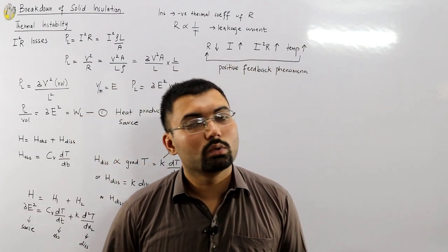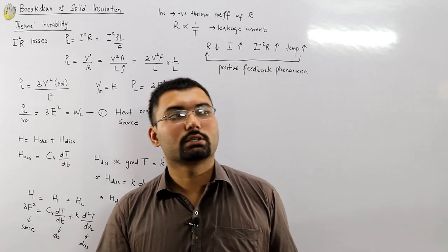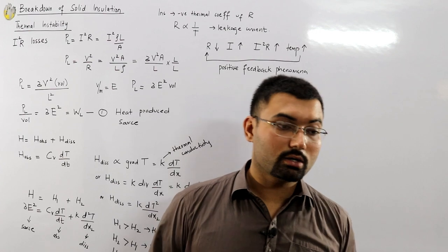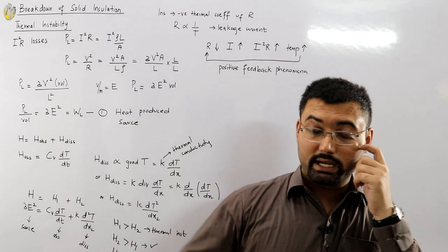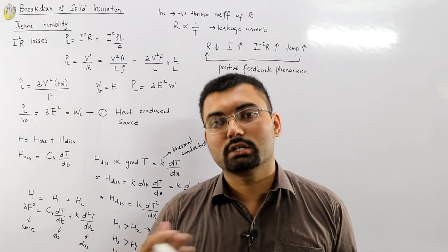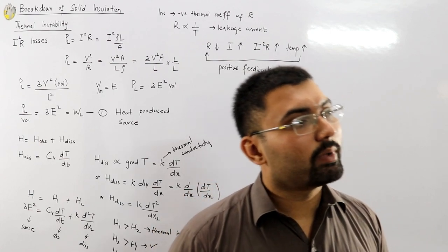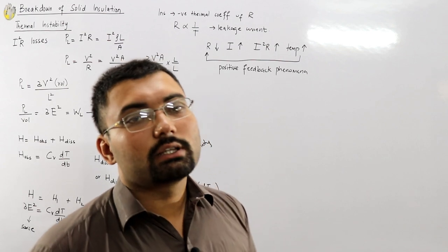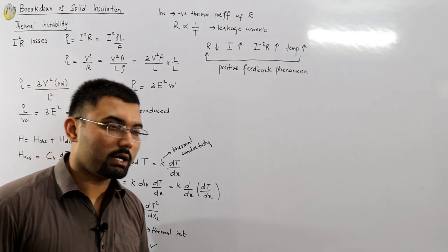Sometimes you turn on the machine, it gets heated up, you turn it off, the temperature goes into the normal limit, again you turn it on and off. This is called cyclic thermal loading. Not a good practice. Once the thermal instability is reached, this is an irreversible process and the machine is not going for a longer run. It may damage any time.